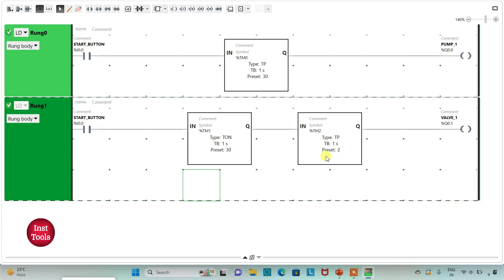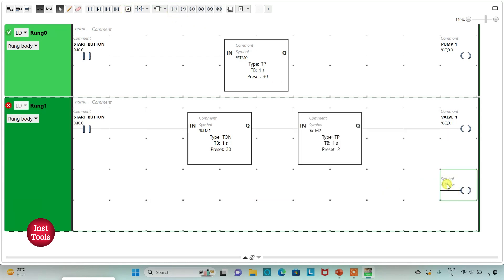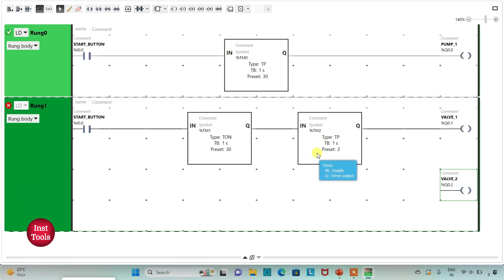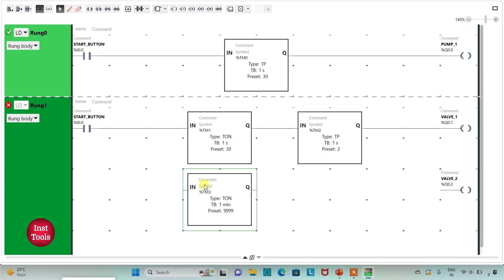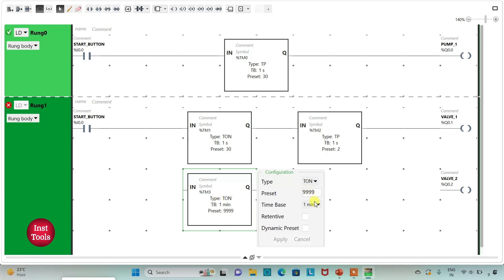Then I will insert one more coil and assign the address Q0.2 with symbol 'Valve 2'. Valve 2 should turn on after Valve 1, so there will be a delay of 32 seconds for Valve 2. For that I will insert another timer for Valve 2, and that should be TON — on-delay timer. I will change the time base to 1 second and preset value to 32 seconds, then click Apply.